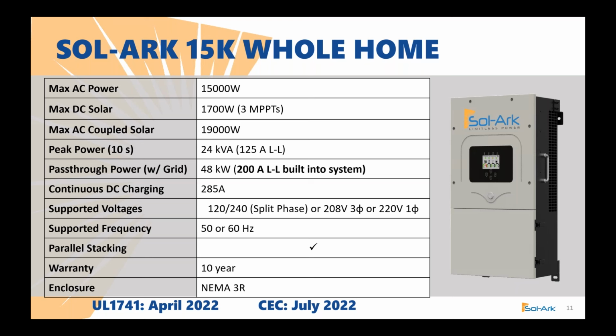It is going to be parallel stackable as well, and it's going to be up to 12 units. That means you can have a continuous total output of 180 kilowatts. That's enough to power a small Walmart. It's going to come with a 10-year warranty and then a NEMA 3R enclosure as well. It's going to be a little larger than our 12K unit. It's going to have about 20 extra pounds of weight added into it and about an inch more in depth, but it's going to look very similar to our previous units.